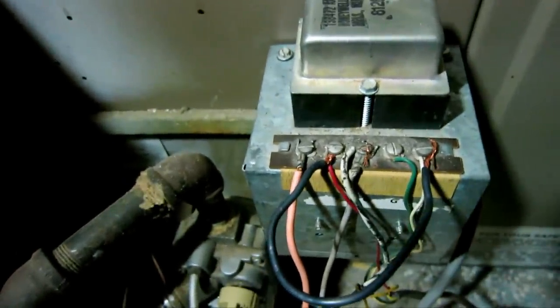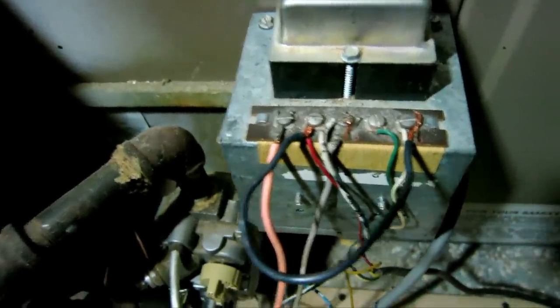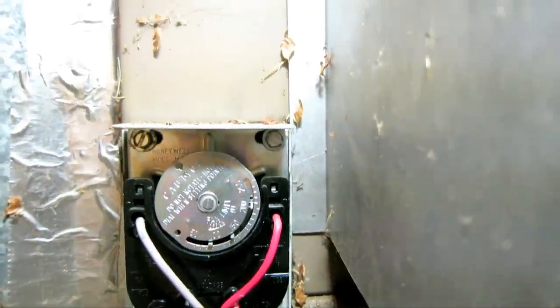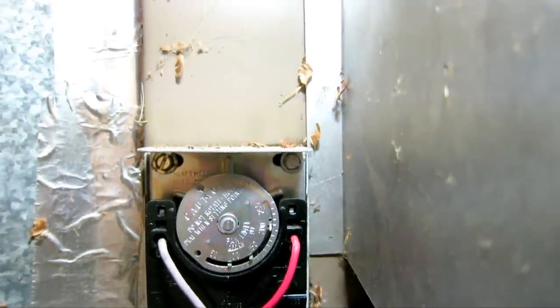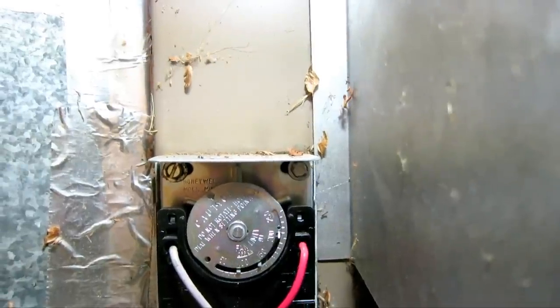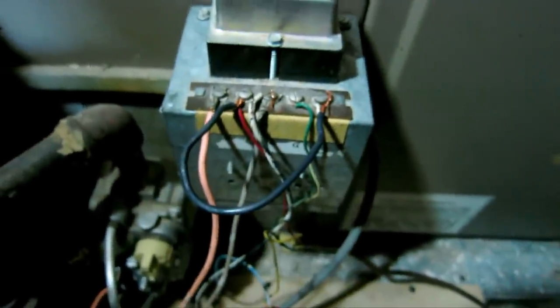So as you see I connected the white, I mean the jumper between white and red. Let's go over here. You can hear that the furnace is kicking on and it should be turning as the temperature rises. But as you can see it is not moving at all and the fan motor of course is not coming on. So I now know that that is a possibility that it is bad.